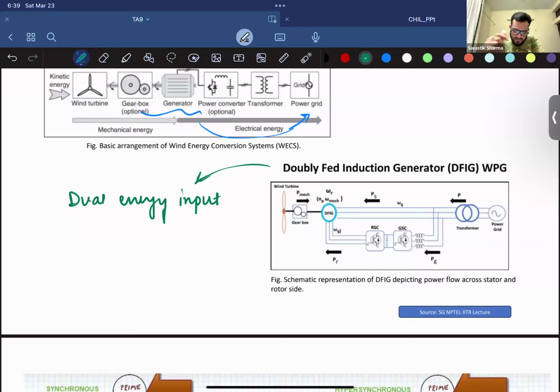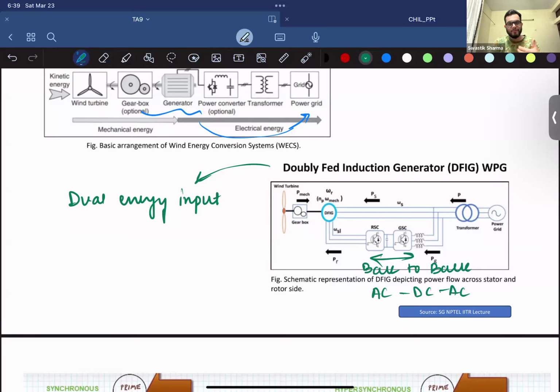So using this DFIG, we use this back-to-back converter, which is nothing but an AC-DC-AC converter. This is a kind of converter used to enable two-way power flow to and from the stator and rotor. And this is only possible with this DFIG generator in the slip ring form or wound rotor form.